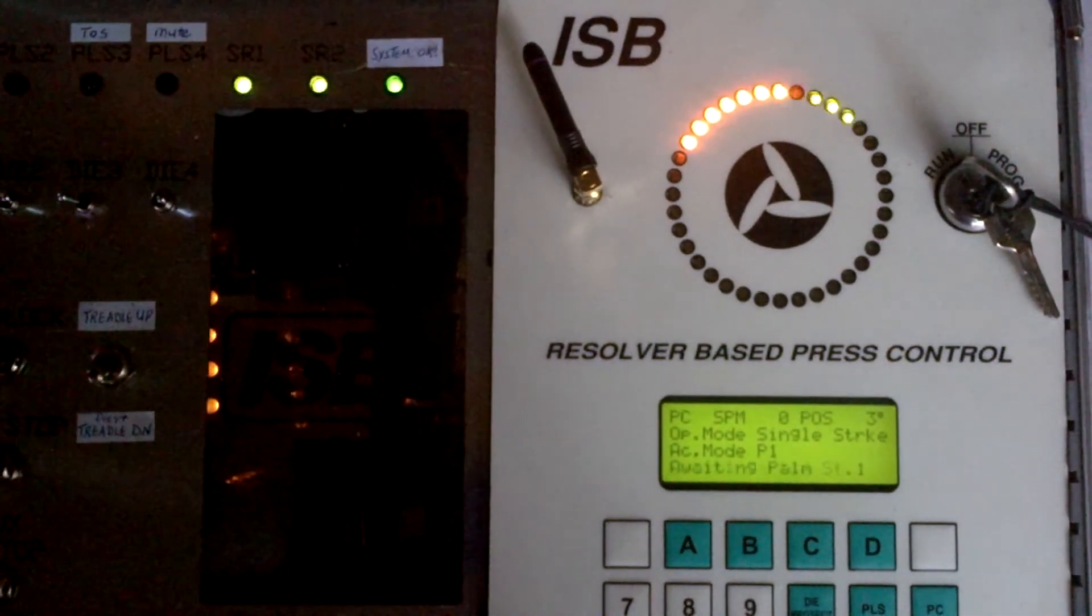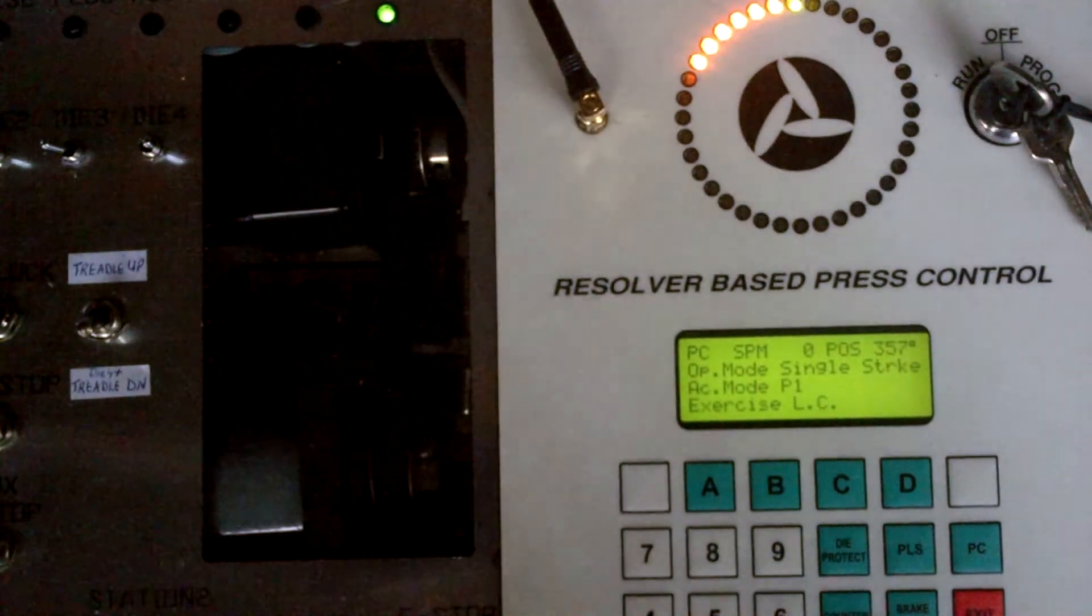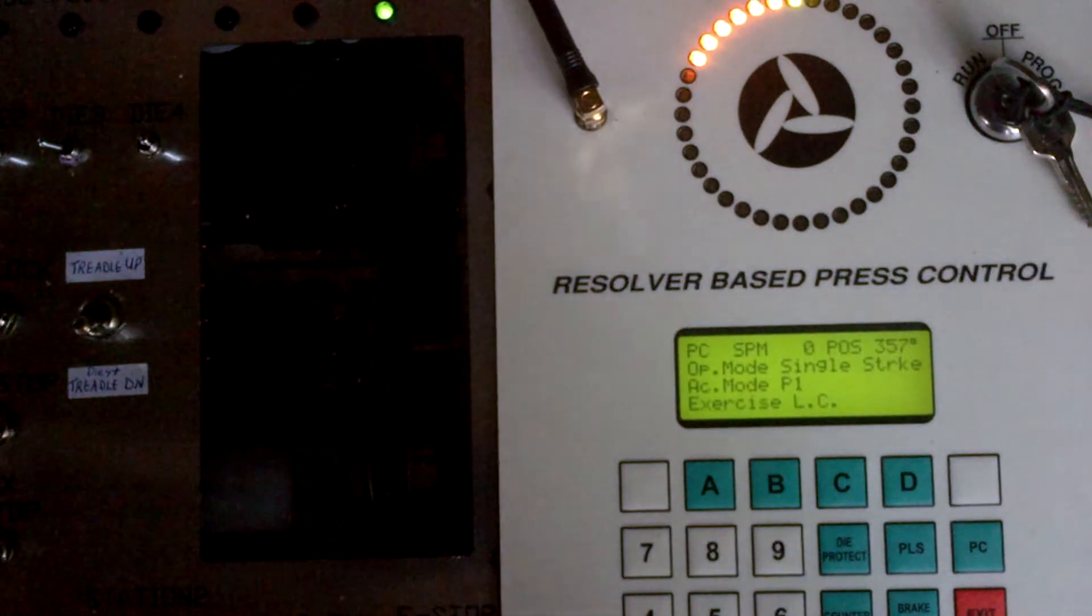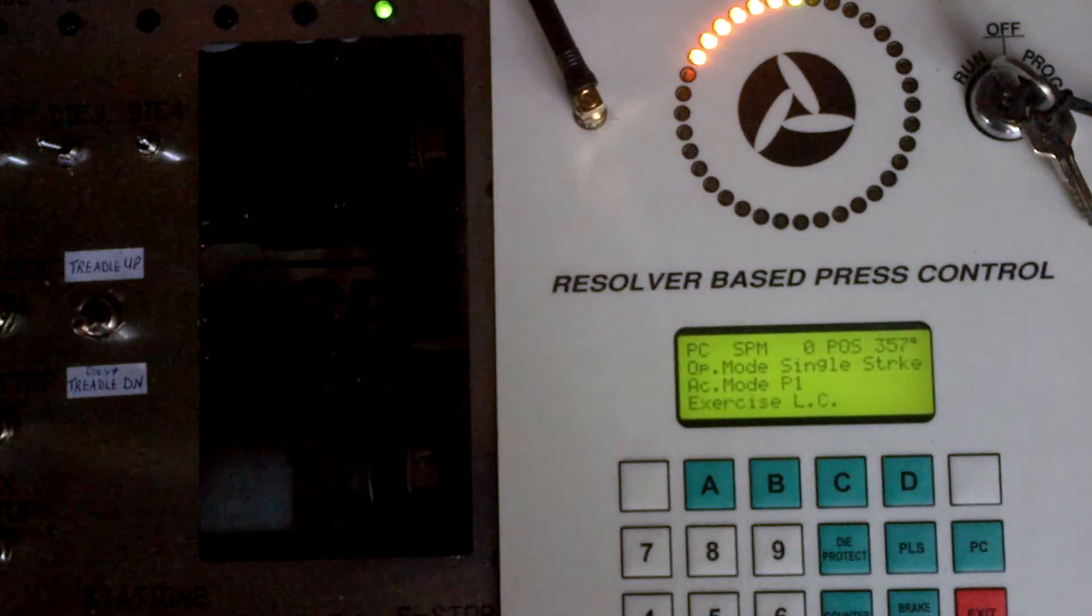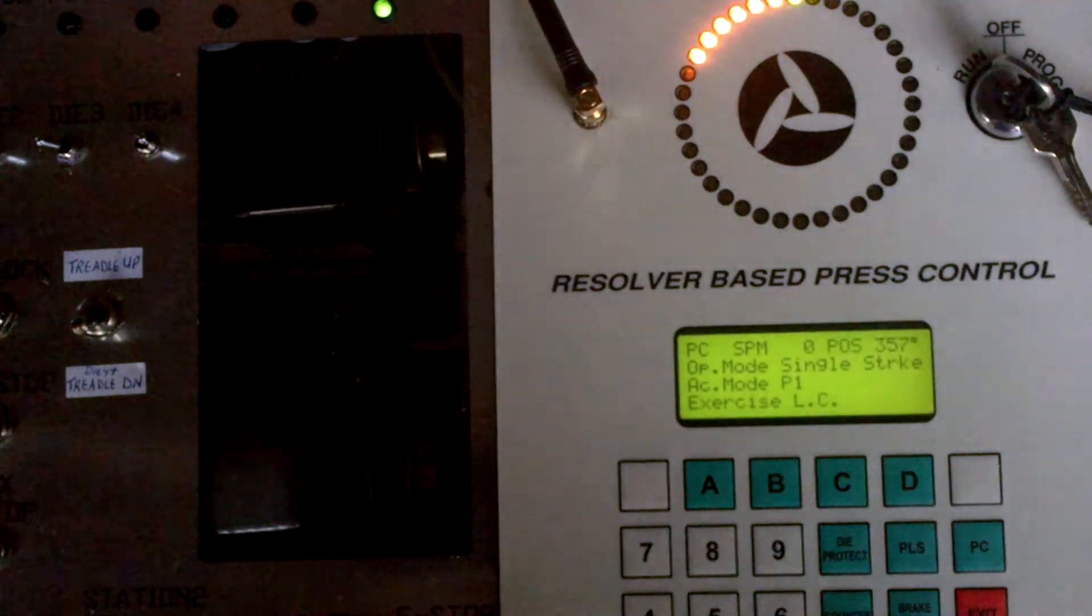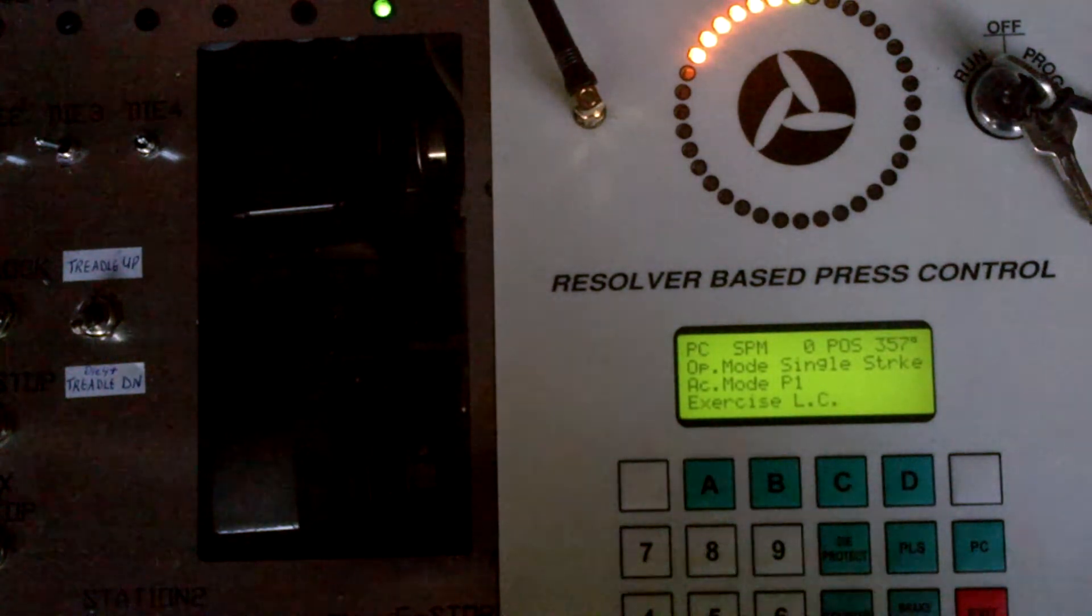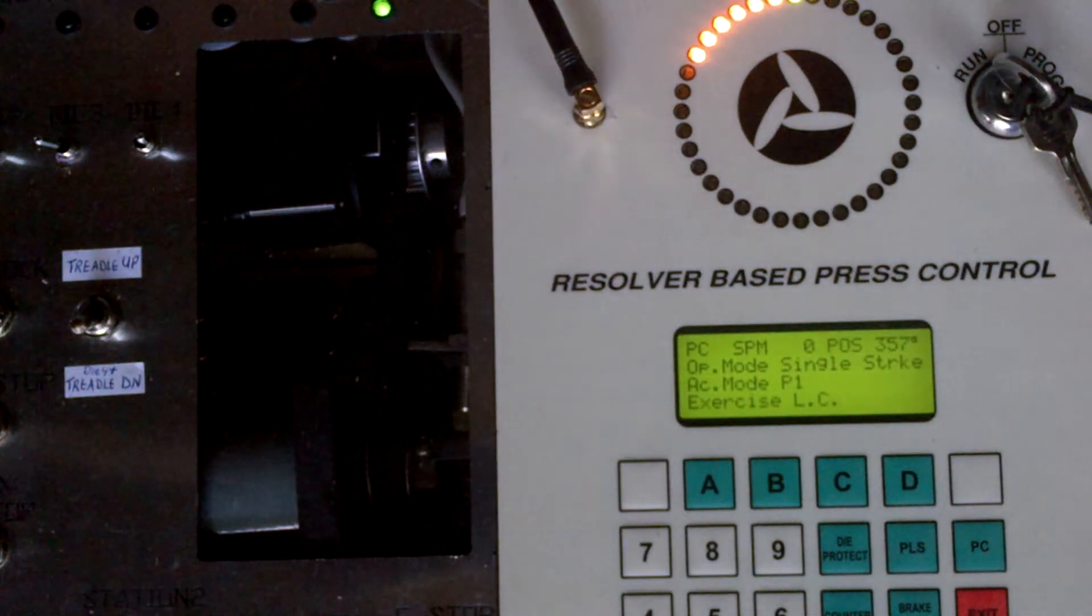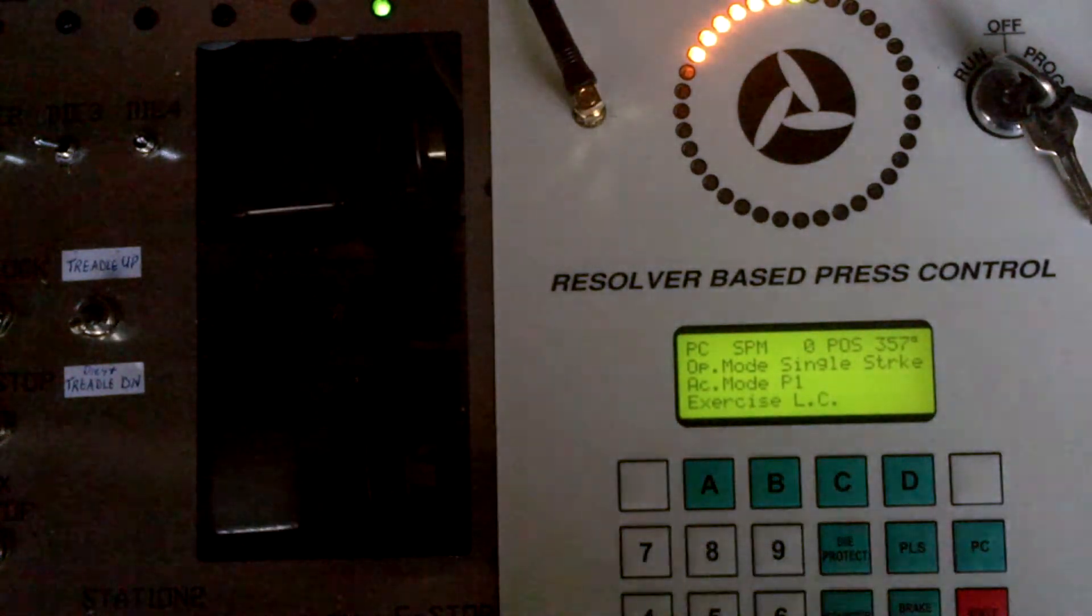And if the position indicator was 330 degrees, the next stroke is going to be 335 degrees or thereabouts. The next stroke will be somewhere in the 340s and the 350s. And if you make 6, 7, 8, 10 strokes, you'll eventually see every stroke getting closer to zero degrees. Once it hits zero degrees or close to 357, 358, within a few degrees of zero, you have zeroed your resolver. There's nothing more you need to do.